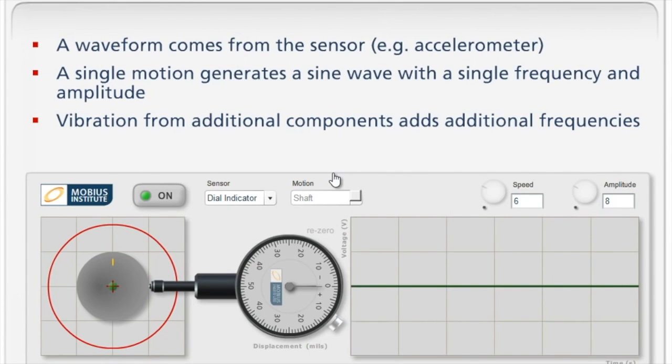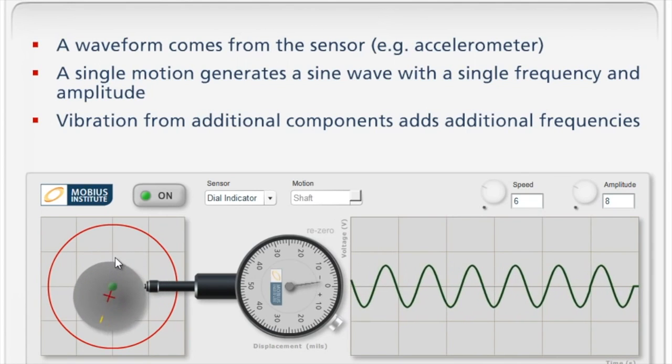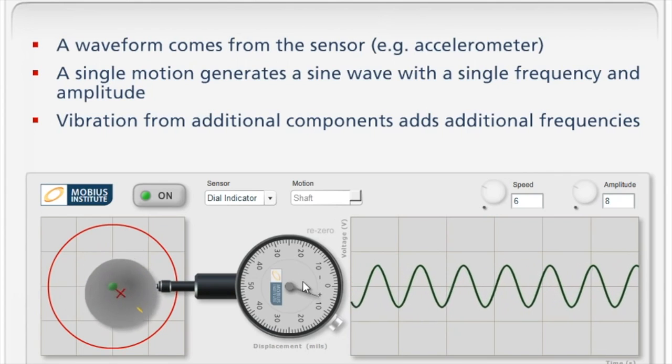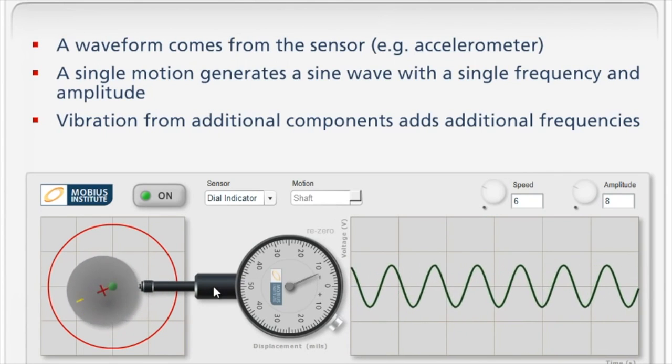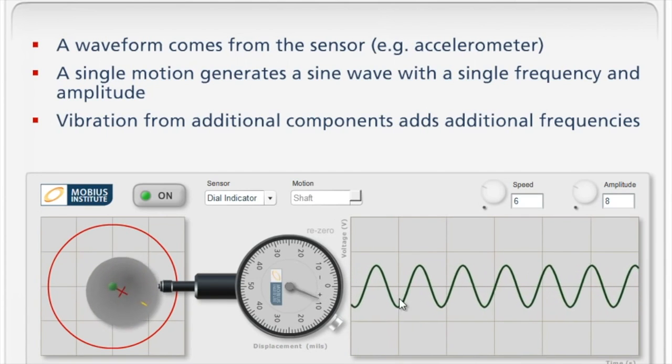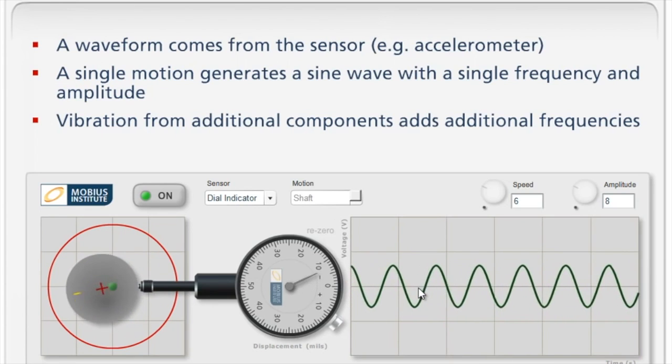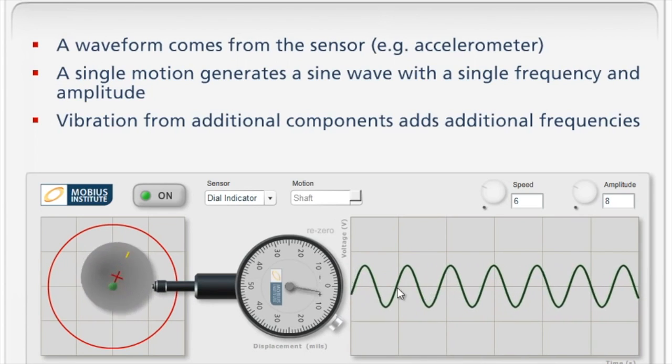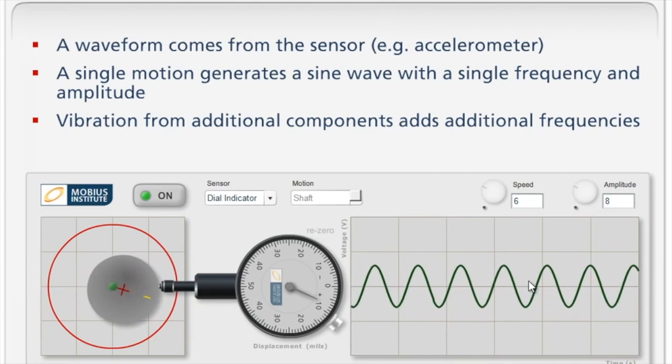Our sensor is sensing the motion in this particular case on the bearing itself. Imagine if this was the shaft inside the machine, and I exaggerate some of the motion. There's the shaft moving around in that circular motion, perhaps because of unbalance or a bent shaft. For simplicity's sake, we've put a dial indicator on the shaft. As the shaft moves back and forward, it pushes the plunger in and out. We see the needle move and we get this pattern. That pattern is a sine wave, a pure sine wave with a single frequency and a single amplitude.